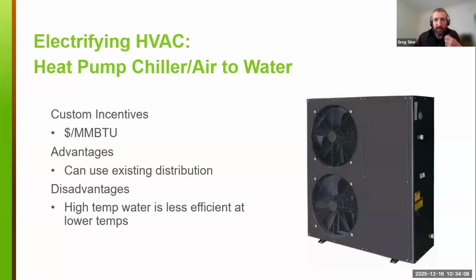Air to water heat pumps or heat pump chillers are a great solution, in particular if you have an air cooled chiller. These can be used to replace that, so they can generate heated or chilled water. It's a good potential partial electrification strategy. They can also work well as a boiler replacement or in tandem with an existing boiler to do some pretty significant work in the heating season.